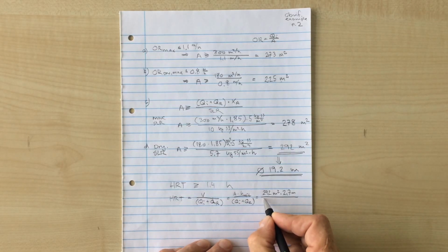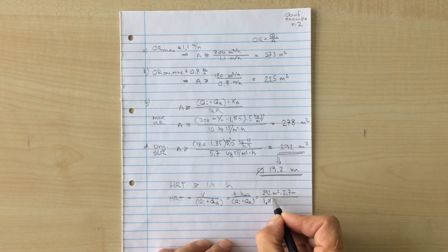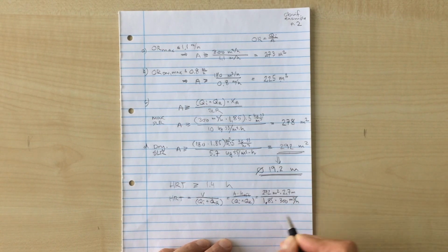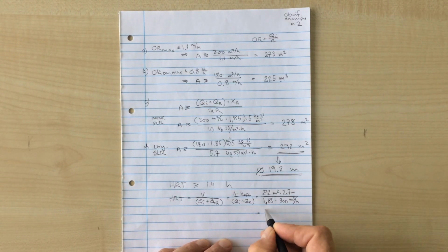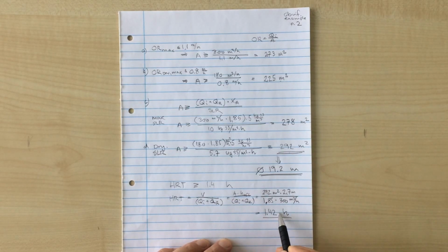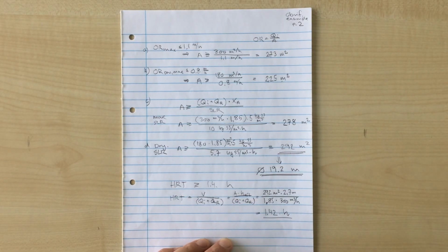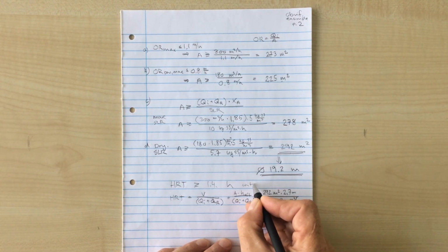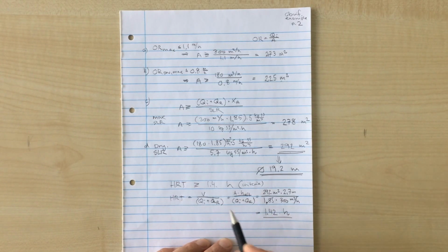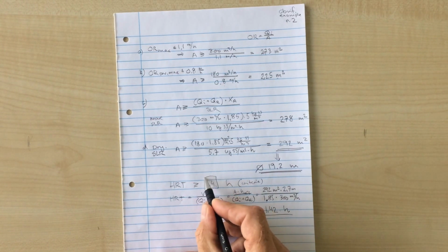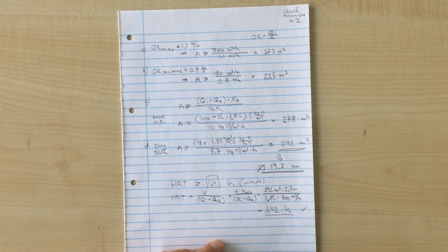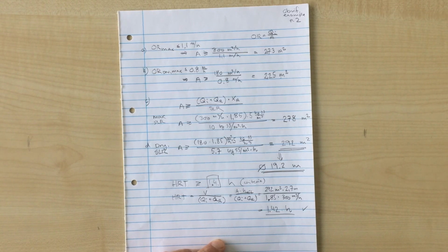So this will be my peak flow, 1.85 times 300 cubic meter per hour. Calculating this gives me a value of 1.42 hours, so just a little bit above the criterion. And I will say, well, if I round off, I will get 1.4. So this criterion is just acceptable, just okay.